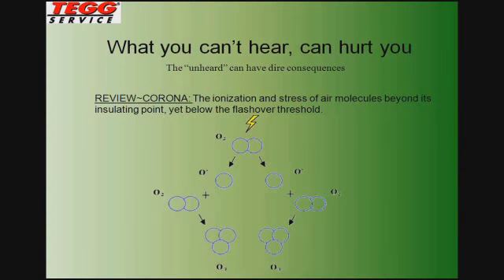The third anomaly that I mentioned was corona. And corona is not the bad beer from Mexico, and that's a bad joke, but somebody at our office uses that. Corona is merely the ionization of air molecules due to stresses of the expanding and collapsing magnetic field on higher voltages in electrical systems. And what the ionization process does, it stretches the air surrounding that termination beyond its insulating point, because air is a very good insulator under normal conditions, but it doesn't stress it to its flashover point.